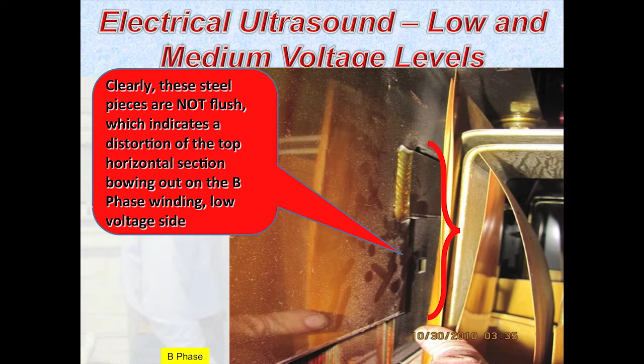When we look at the coil in question, it's a totally different story, and I think you can see this a little better. This horizontal piece right here, where it meets the vertical piece, there's the clamping steel. There's an elevation difference of almost a quarter inch between those two pieces. So when it came together, instead of being nice and flush on this joint, it was offset, and it went out like that.